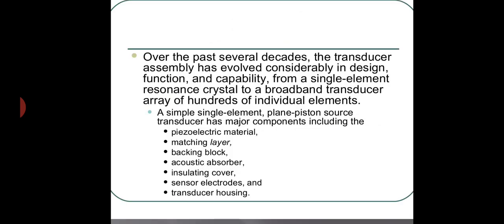Over the past several decades, the transducer assembly has evolved considerably in design, function, and capability, from a single element resonant crystal to a broadband transducer array of hundreds of individual elements. A simple single element plane piston source transducer has major components including the piezoelectric material, matching layer, backing block, acoustic absorber, insulating cover, sensor electrodes, and transducer housing.